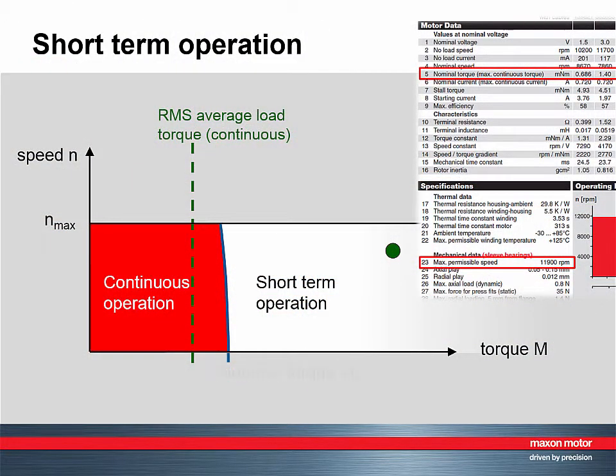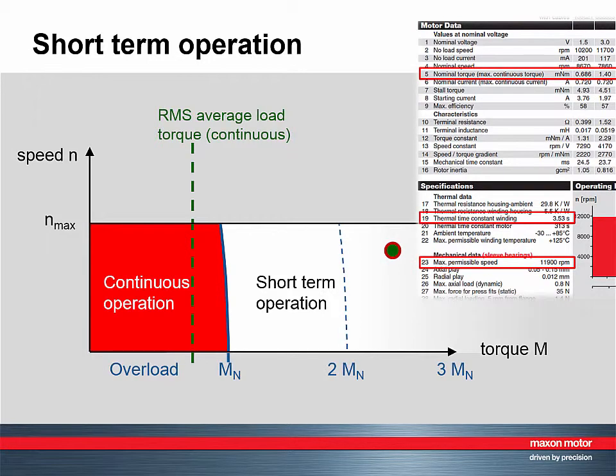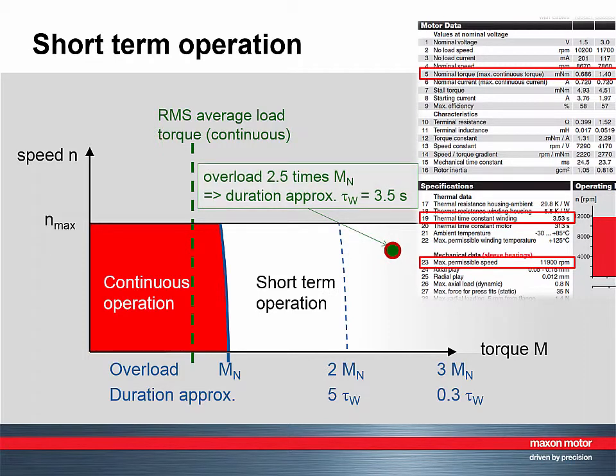Higher torques than nominal are possible, but only for a limited amount of time. How long an overload situation may last depends on the amount of overload torque and the motor type. As a rule, the larger the motor, the longer the overload can be. Typically, overload can last several seconds, as indicated by the thermal time constant of the winding. Roughly speaking, a motor can support two to three times the nominal torque for periods up to this thermal time constant.